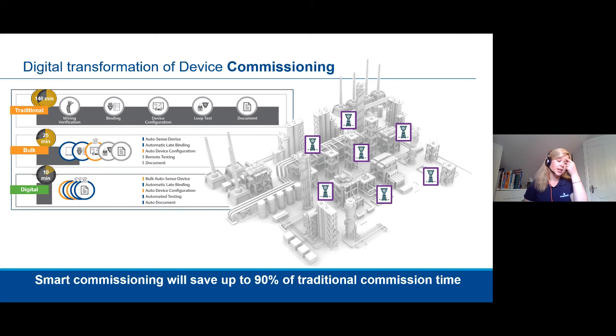If any of you utilize or have heard of Delta V, you can eliminate all of this work by digitizing your commissioning, auto-sensing bulks of devices, automating the binding to the control modules. You have your automatic configuration and testing, and then auto-document everything in a report at the end, saving 90% of traditional commissioning time.